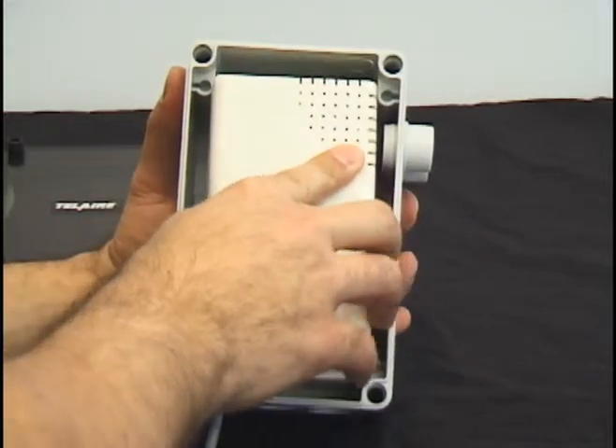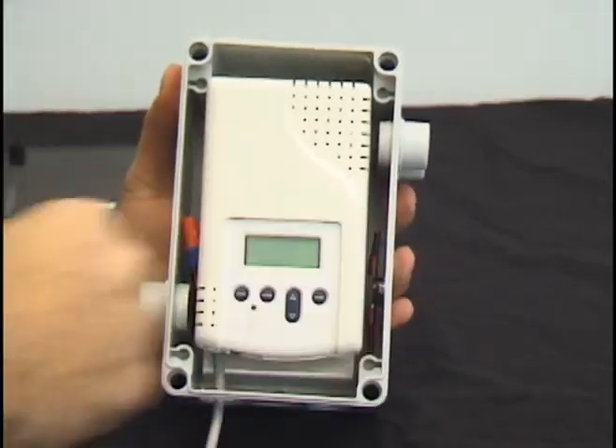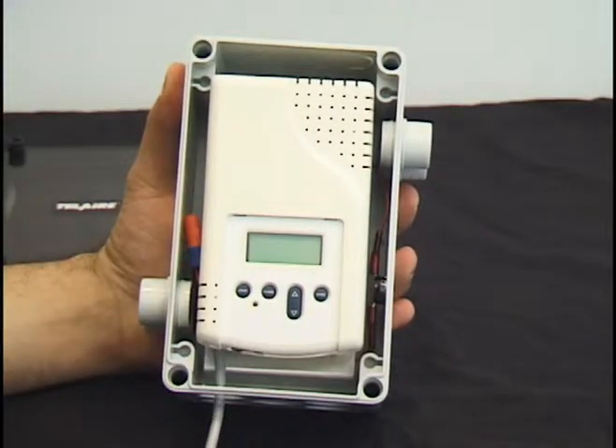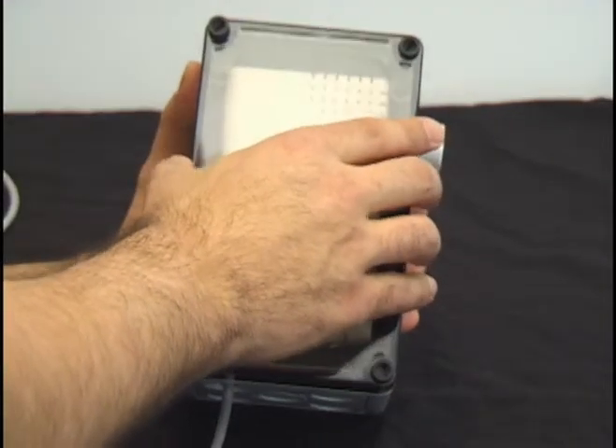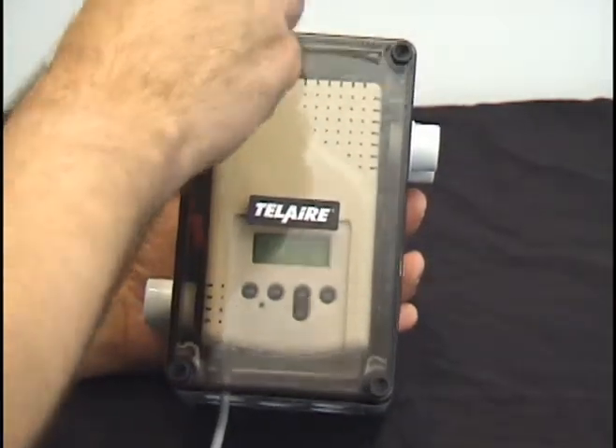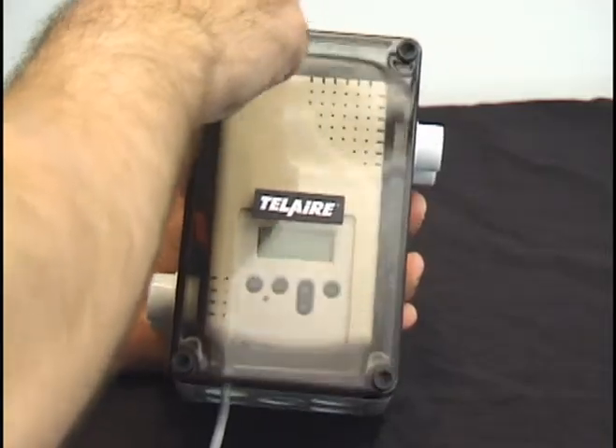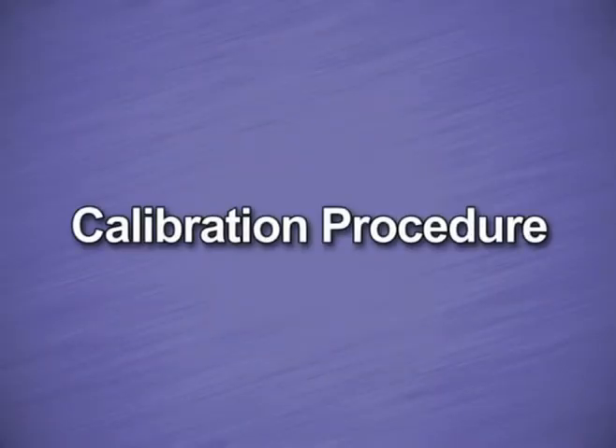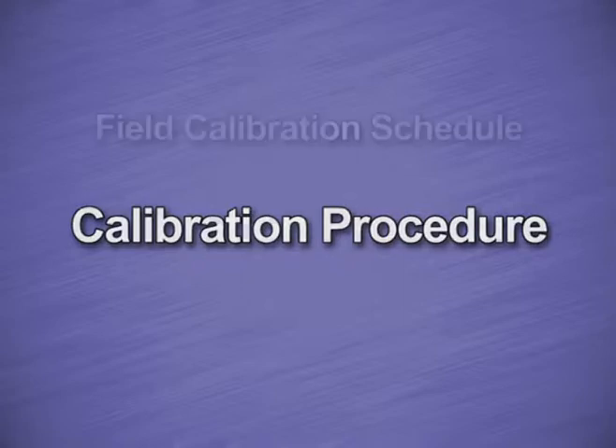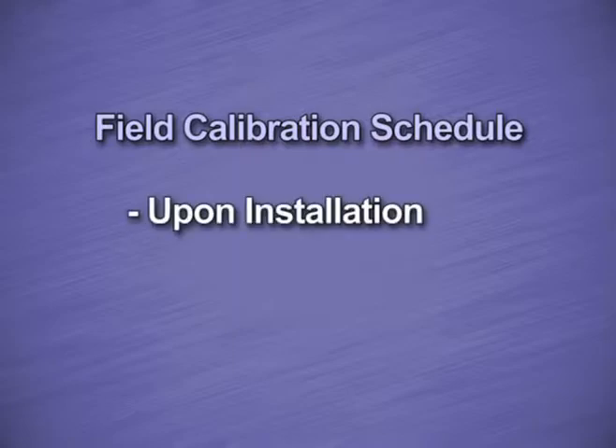Next, snap the sensor into the mounting plate. The sensor locking cover is not used. Secure the cover of the outside air box and ensure that the conduit connection is sealed. We are now going to cover the calibration procedure. To ensure accurate readings upon installation and for the life of the sensor, field calibration is required. Calibration of the dew point sensor should be done upon installation and annually thereafter.